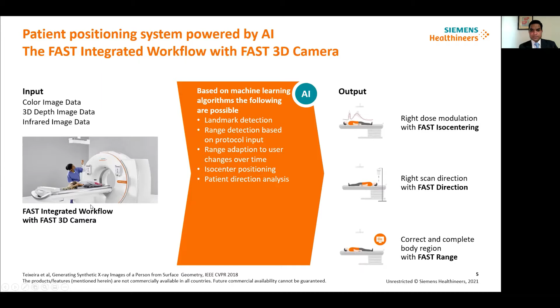This 3D avatar is then used as an input for a number of different algorithms. A couple of them are specifically to determine automatically the scan direction, whether it's a head-first or a feet-first scan, and to automatically determine the ISO center of the patient for the scanning. And as we know, a precise determination of the ISO center not only improves the image quality, but also helps in reducing the dose for the particular exam.